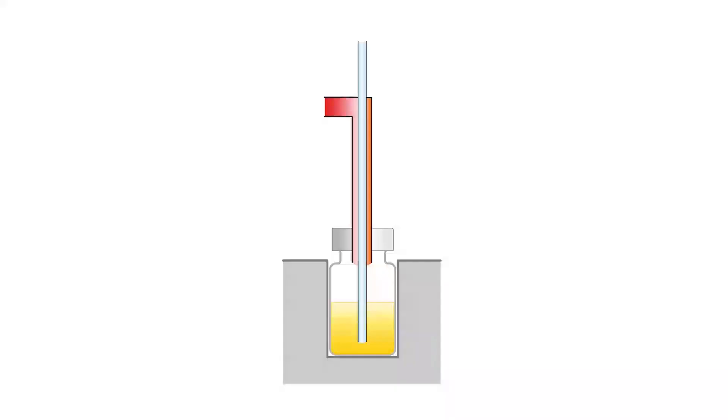What happens inside? The Karl Fischer oven heats the sample and the water contained in it evaporates. A stream of dry carrier gas transfers the water to the titration cell. There it is determined by coulometric Karl Fischer titration.